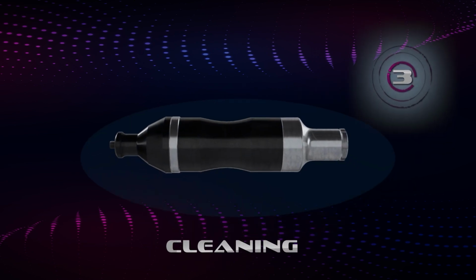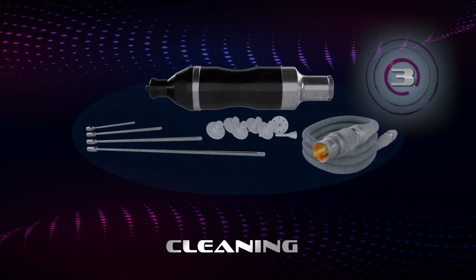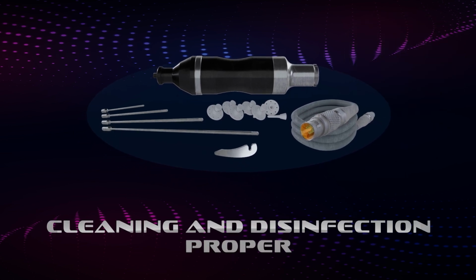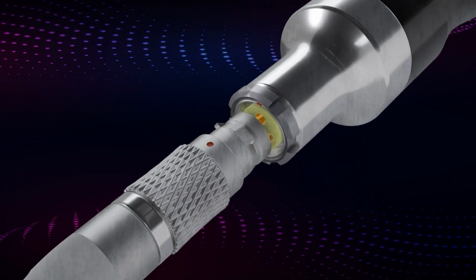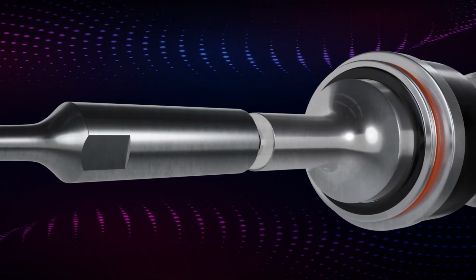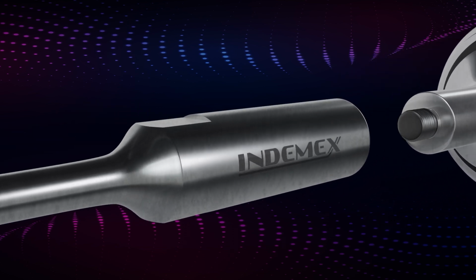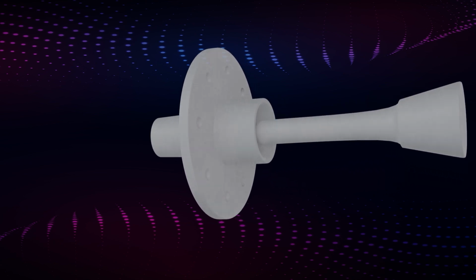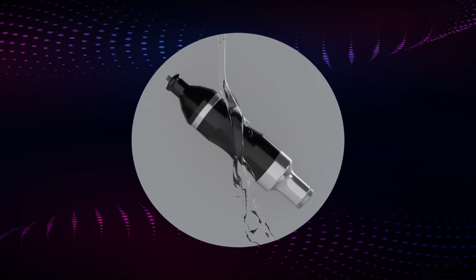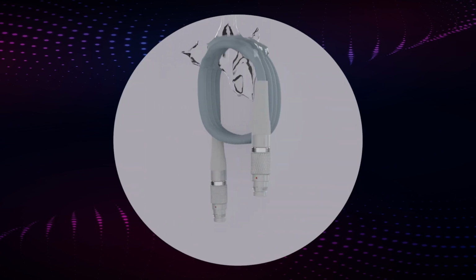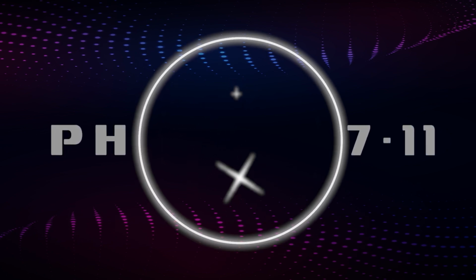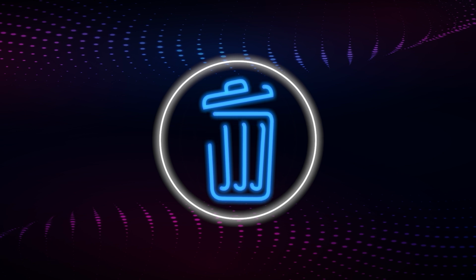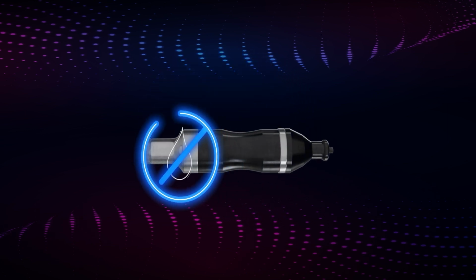3. Cleaning the handpiece, cable, sonotrodes, protective cords, and wrench require proper cleaning and disinfection. Follow these steps to keep them in optimal condition. Turn off the device and disconnect the handpiece cable. Remove the sonotrodes from the handpiece as described in our assembly section. Disassemble the protective cords by separating the two pieces. Wash and scrub externally the handpiece, sonotrodes, cable, and protective cords using a cleaner with a pH in the range of 7 to 11. Make sure to remove all visible residues, avoiding wetting the connectors.